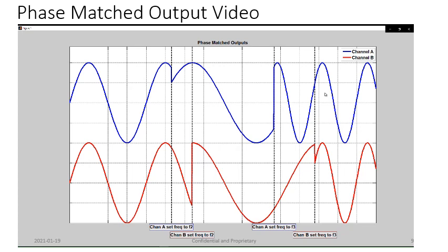Now, of course, if we attach cables with different physical characteristics to the outputs of those two channels, their phases would not match. The firmware of our Model 855 supports a command that allows to compensate for mismatching cable length and therefore achieve phase matching independently of the cabling used at the output of the channels.